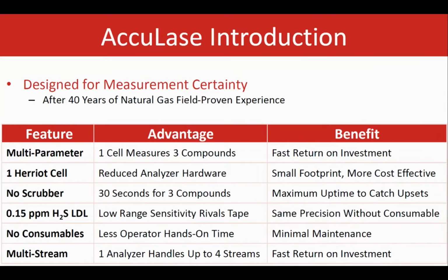No scrubber is used in the system, so no consumables. Also, fast measurement of all 3 components. It is a very sensitive method with a low LDL of 0.15 ppm, which is a lower detection limit, for H2S as an example. It can also analyze multi-streams for all 3 components in the same unit. Therefore, it is a fast return on investment.